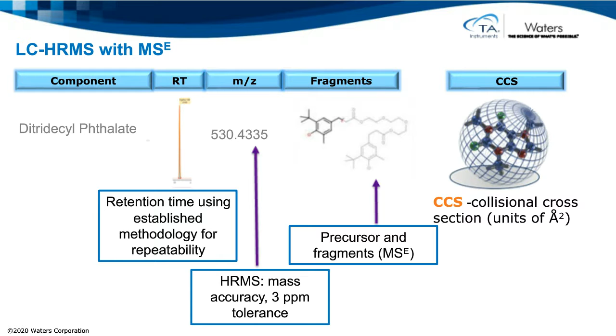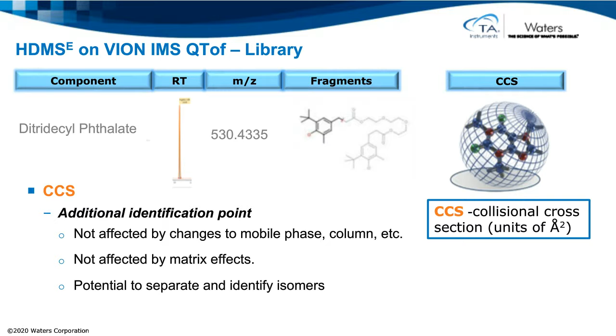This is where we can turn to a value called the collisional cross-section of an ion, the CCS value. The CCS values can be obtained by a technique called ion mobility spectrometry. It can be advantageous as an additional identification point, helping to reduce false positives when screening. Unlike retention times, CCS values are not affected by changes to mobile phase or by column or by matrix effects. Furthermore, where accurate mass alone would fail to separate isomers, CCS values could potentially be used to separate and identify any isomers present. Therefore, the additional CCS values to the extractables and leachables screening library can help aid successful targeted screening.